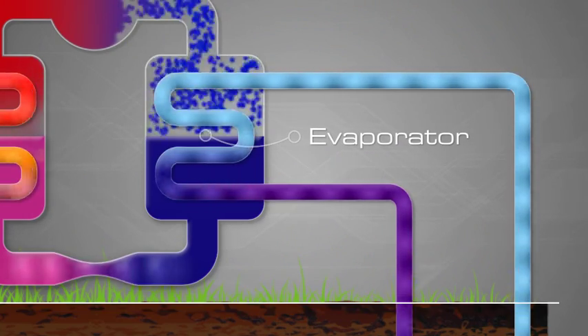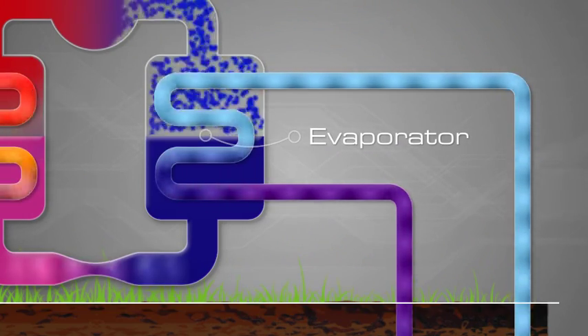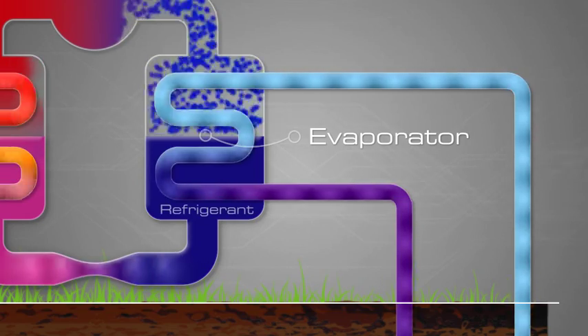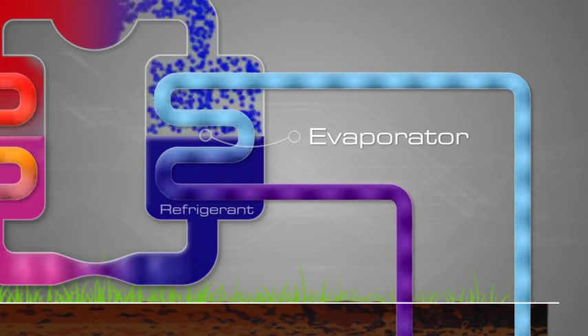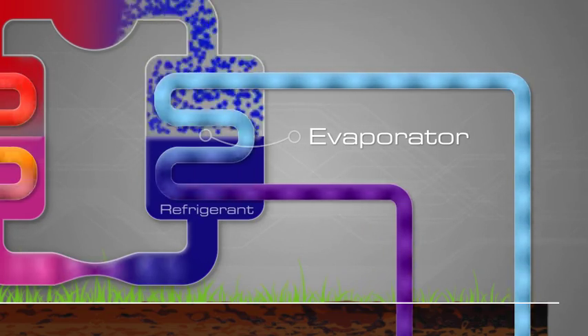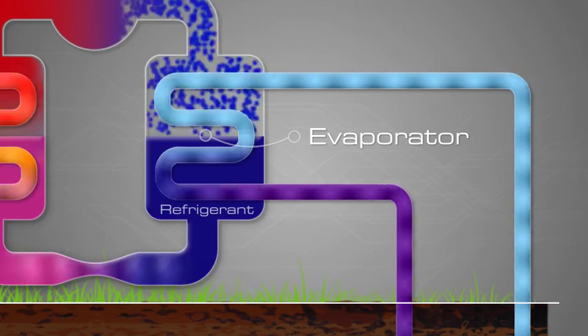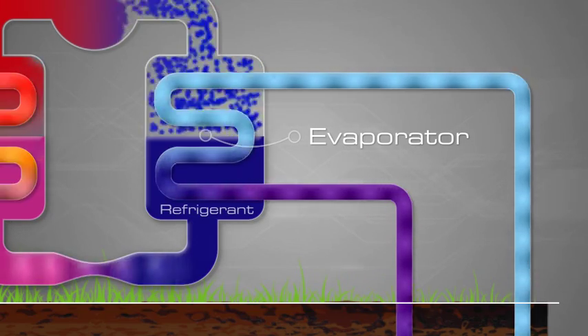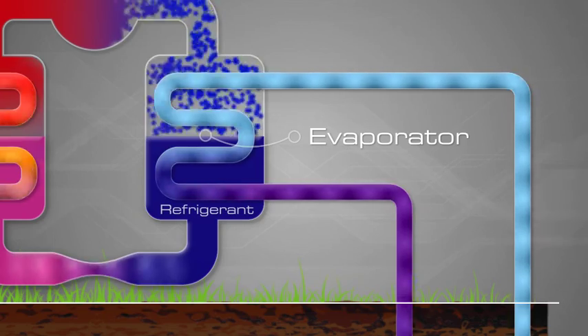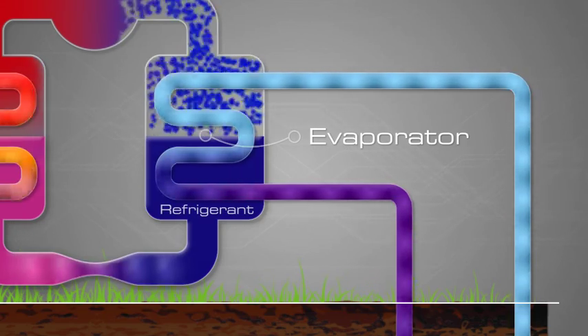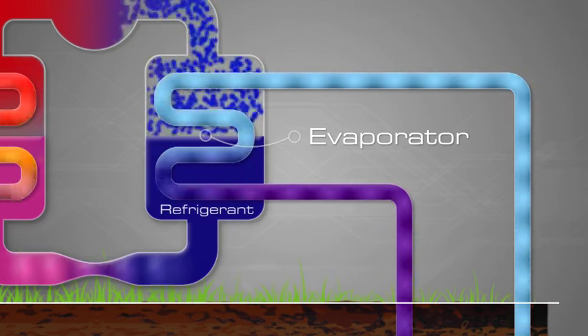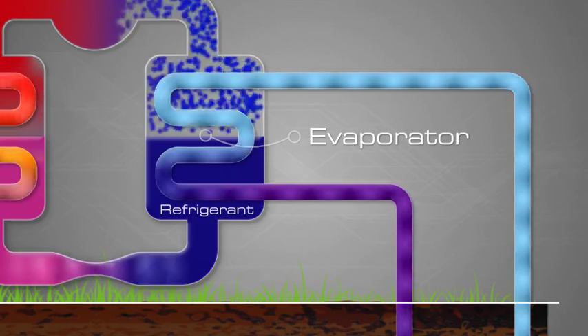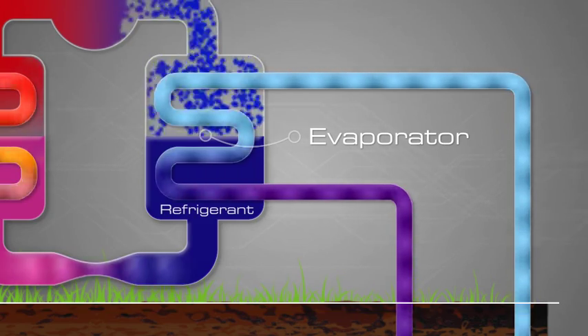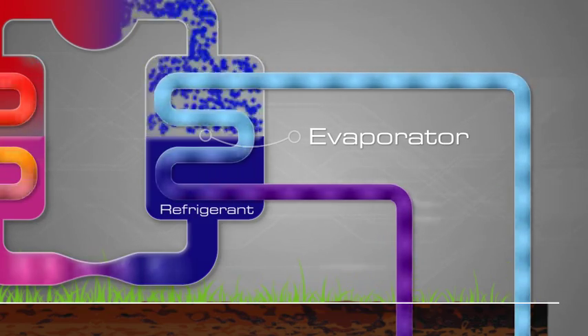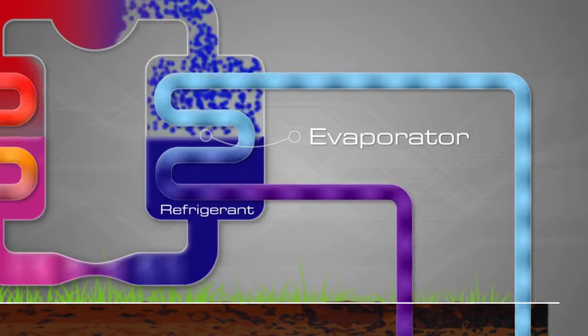Within the secondary, sealed side of the evaporator heat exchanger is a refrigerant, which acts as a heat transfer fluid. When the water antifreeze mixture enters the evaporator, the energy absorbed from the ground is transferred into the refrigerant, which begins to heat up and turn into a gas. The refrigerant never physically mixes with the water antifreeze mixture. They are separated like sandwich layers by the plates of the heat exchanger, which permits the heat transfer.